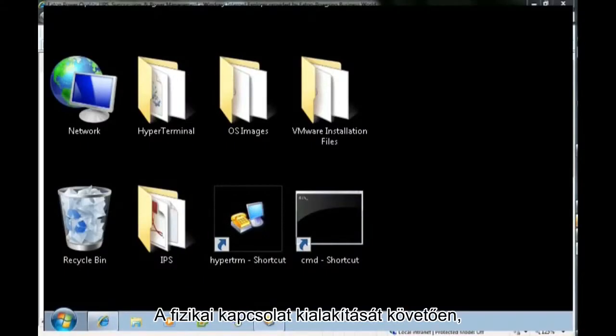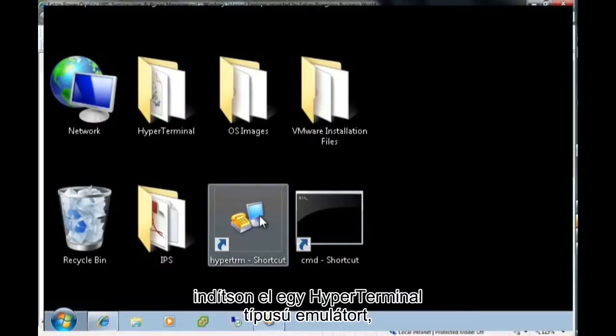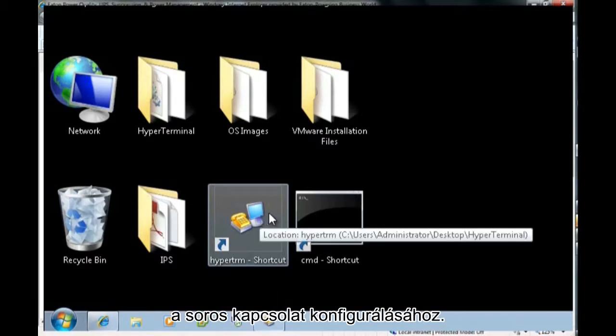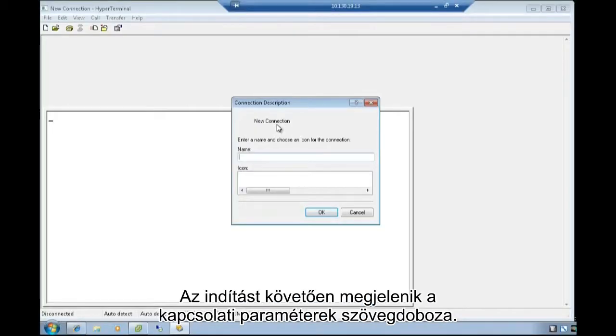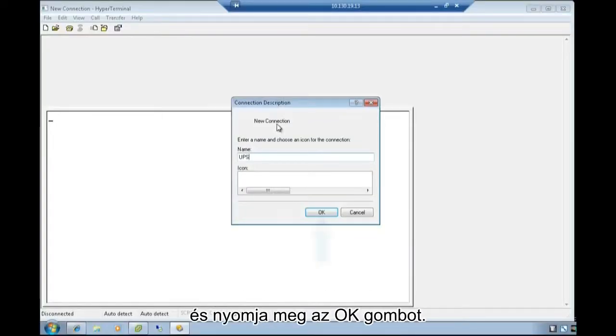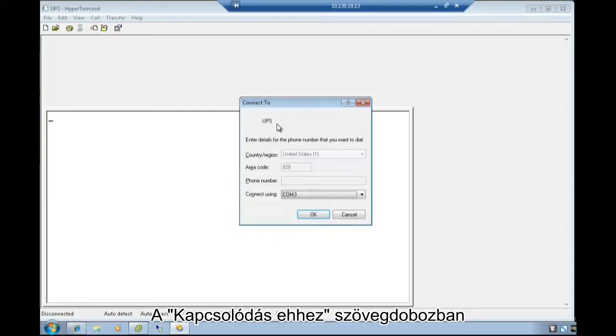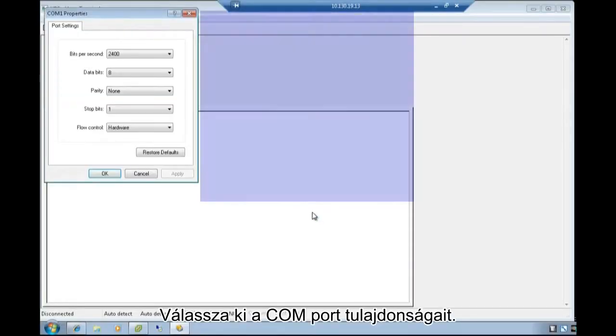Once the physical connection is made, launch a hyperterminal type emulator to configure the serial connection. Once launched, the connection description text box will appear. Enter the name desired for the UPS system and press OK. Using the Connect to text box, choose your designated COM port for your connection and select OK. Select the COM port properties.